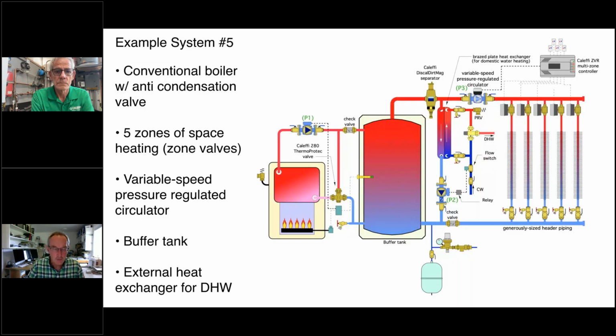If we have a conventional boiler, we don't want to cause sustained flue gas condensation. Caleffi has a valve. It's called a ThermoProtec valve. It's a thermostatic valve. And what this does is it blends hot water coming out of the boiler with cool water to get a temperature returning to the boiler that is high enough to prevent flue gas condensation. Typically, that should be about 130 degrees. And these valves are available with different settings, but that's one detail. Another detail.